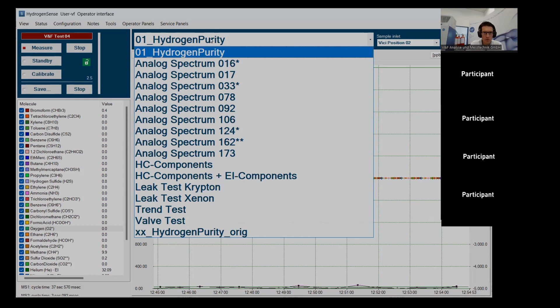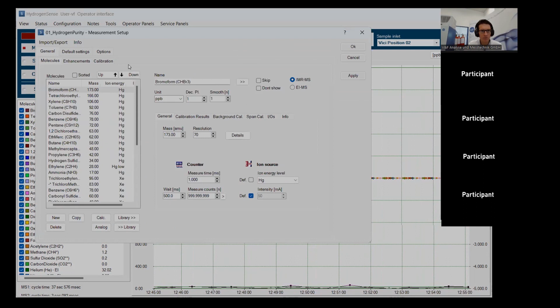So I've showed it before. You can now have all these measurement methods here. So this one is especially designed for hydrogen purity. All of the molecules implemented here are compliant to this ISO standard. I can show you in principle. Wait, give me a second. There it is. So in principle, everything that is done in this method is editable. For example, if you want to have a method which only includes ammonia, you can have that. It's not an issue. Just delete everything else and then the instrument will only measure ammonia.